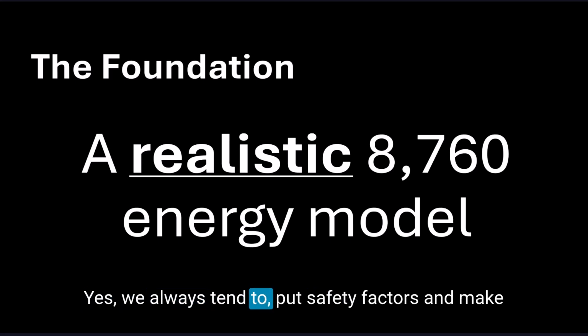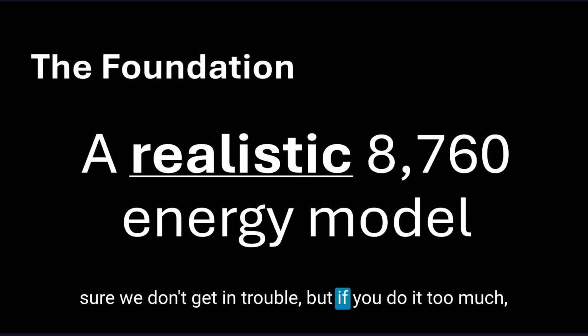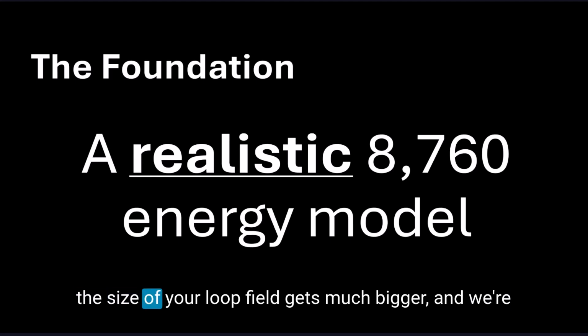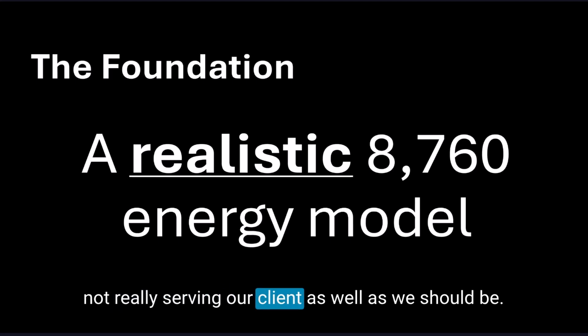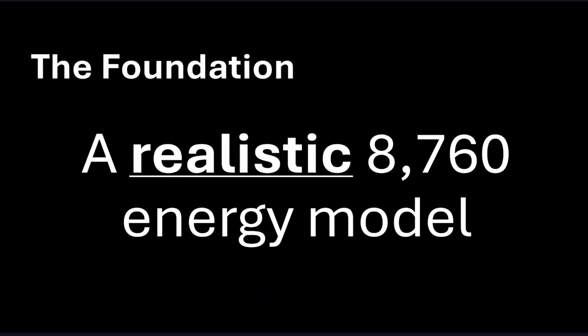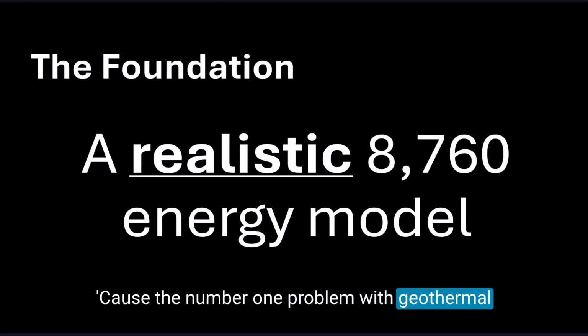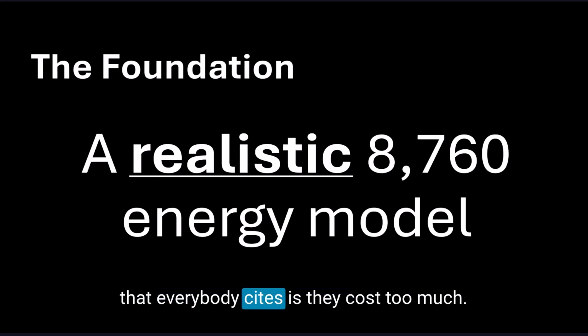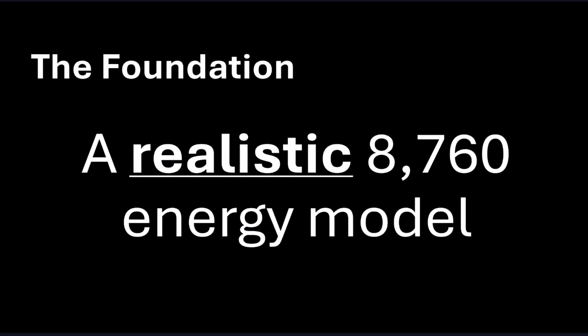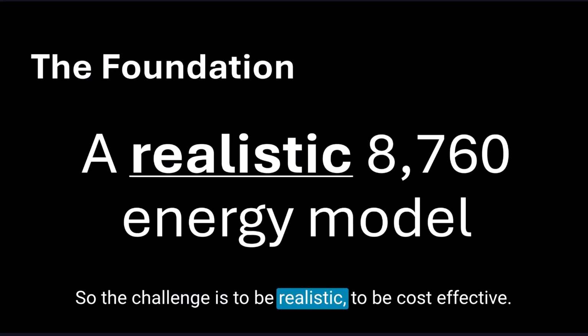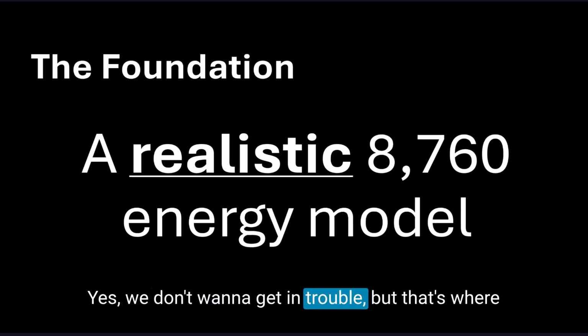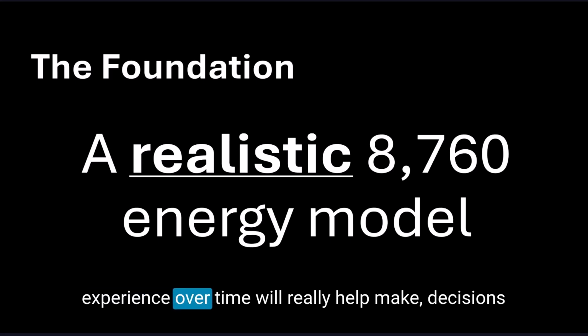Yes, we always tend to put safety factors in and make sure we don't get in trouble. But if you do it too much, the size of your loop field gets much bigger, and we're not really serving our client as well as we should be. Because the number one problem with geothermal that everybody cites is they cost too much. So the challenge is to be realistic, to be cost effective. Yes, we don't want to get in trouble, but that's where experience over time will really help make decisions.